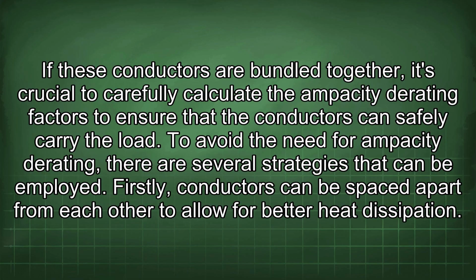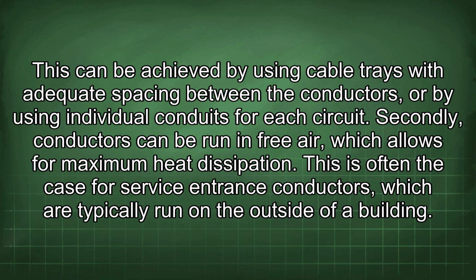To avoid the need for ampacity derating, there are several strategies that can be employed. Firstly, conductors can be spaced apart from each other to allow for better heat dissipation. This can be achieved by using cable trays with adequate spacing between the conductors, or by using individual conduits for each circuit. Secondly, conductors can be run in free air, which allows for maximum heat dissipation. This is often the case for service entrance conductors, which are typically run on the outside of a building.